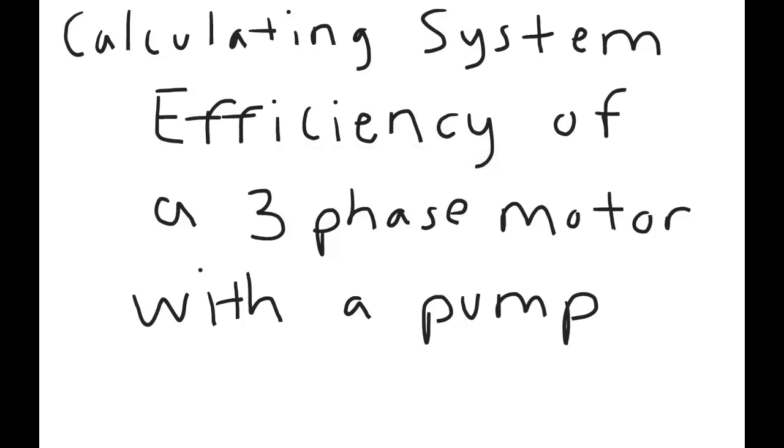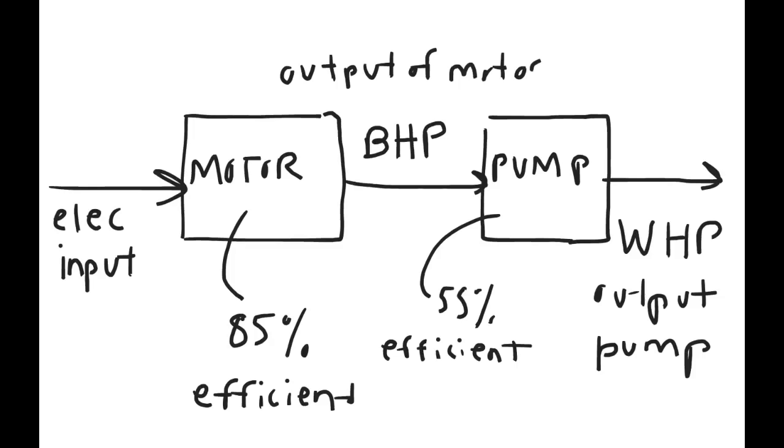I'm going to show you how to calculate the system efficiency of a three-phase motor with a pump. As you can see, we have a motor that is 85% efficient and a pump that is 55% efficient. The electric input going into the motor combined with the efficiency gives you the brake horsepower, the output of the motor, which goes into the pump. Multiply it by the efficiency, you have the water horsepower or the output of the pump.